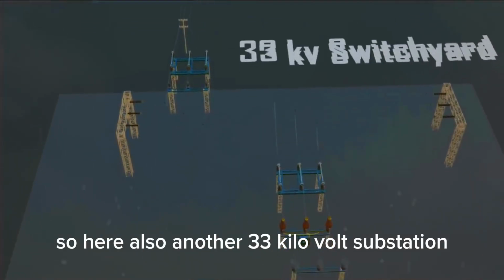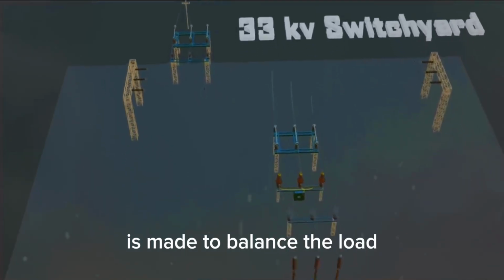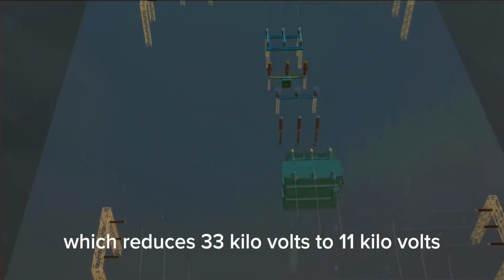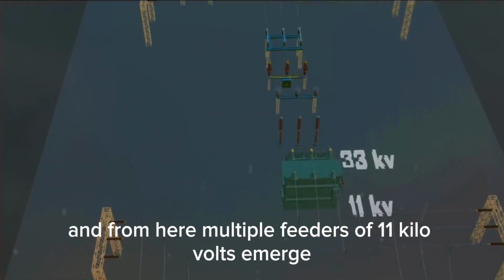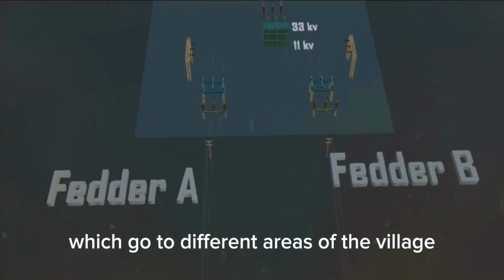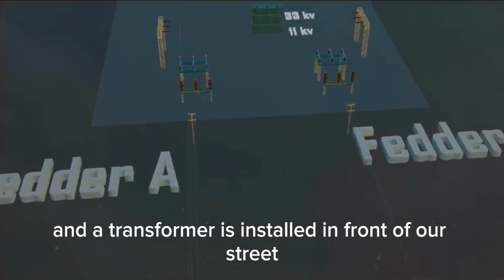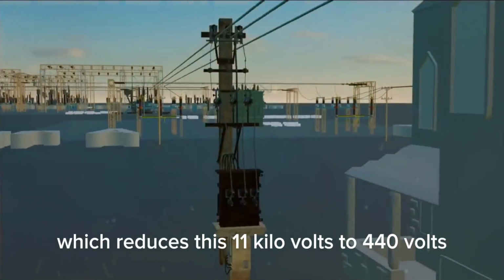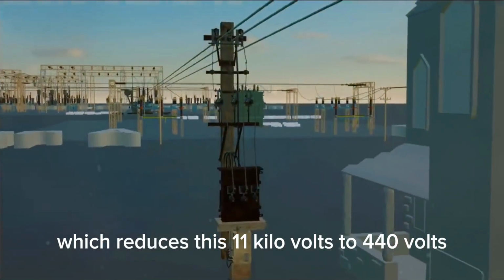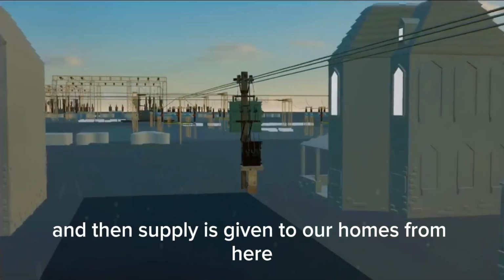So here also another 33 kV substation is made to balance the load, which reduces 33 kV to 11 kV. And from here multiple feeders of 11 kV emerge, which go to different areas of the village. And a transformer is installed in front of our street or corner, which reduces this 11 kV to 440 volts, and then supply is given to our homes from here.